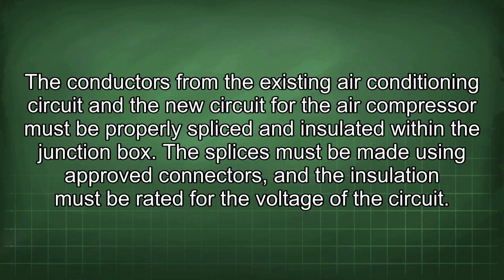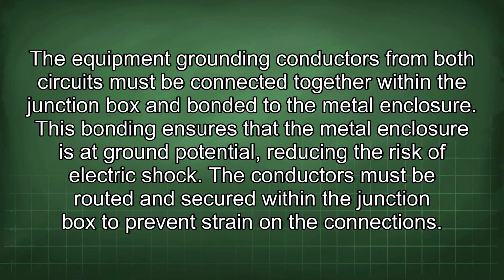The conductors from the existing air conditioning circuit and the new circuit for the air compressor must be properly spliced and insulated within the junction box. The splices must be made using approved connectors, and the insulation must be rated for the voltage of the circuit. The equipment grounding conductors from both circuits must be connected together within the junction box and bonded to the metal enclosure. This bonding ensures that the metal enclosure is at ground potential, reducing the risk of electric shock.